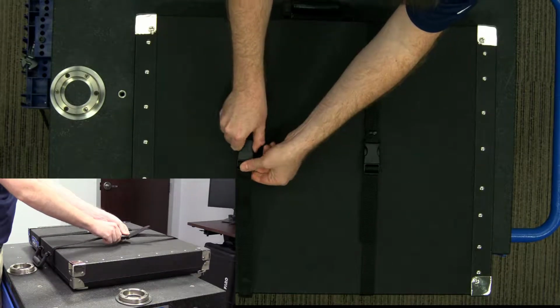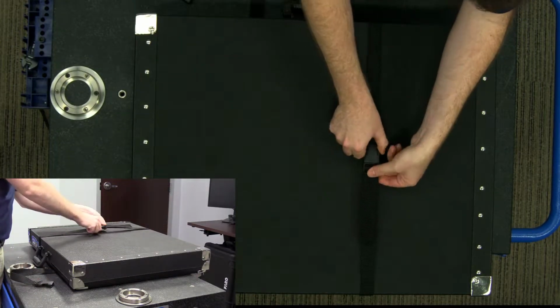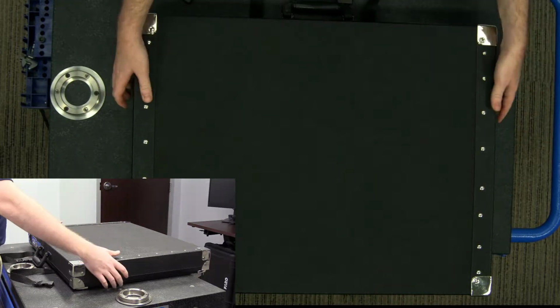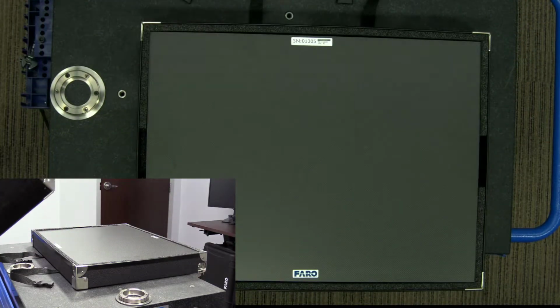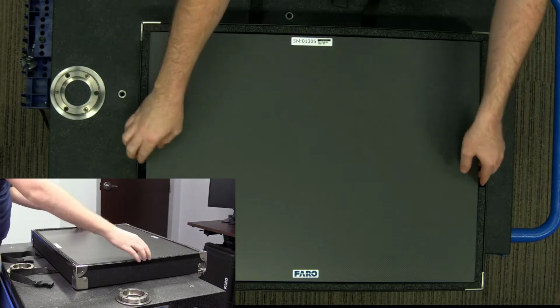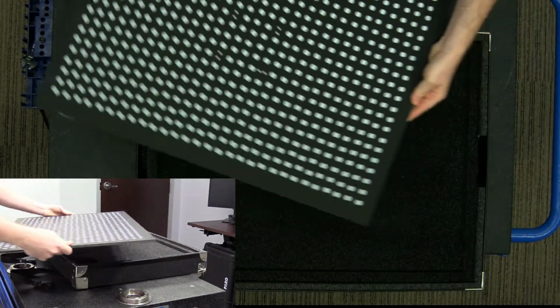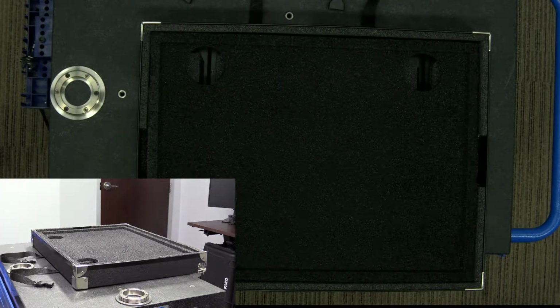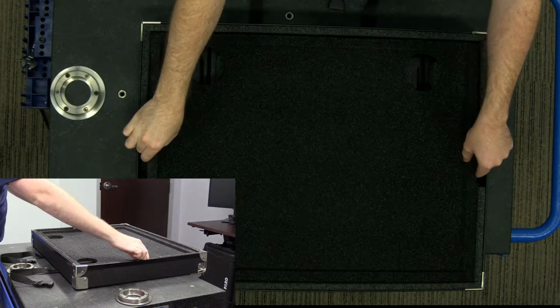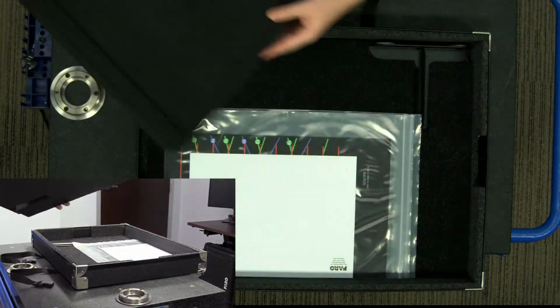measuring environment. Lay the calibration plate carrying case on a flat surface. Unsnap the clips to unstrap the case. Lift off the top of the case. Take the calibration plate out and set it on a flat surface with the white dots facing upwards. Be careful to not touch the white dots. Remove the top foam layer.